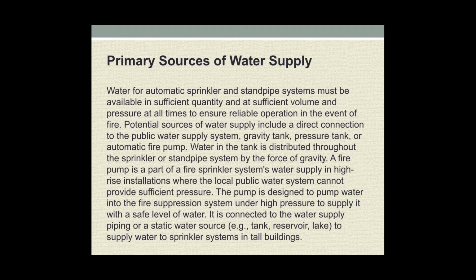Primary source of water supply. Water for automatic sprinkler and standpipe systems must be available in sufficient quantity and at a sufficient volume and pressure at all times to ensure reliable operation in the event of fire. Potential sources of water supply include a direct connection to the public water supply system, gravity tank, pressure tank, or automatic fire pump. Water in the tank is distributed throughout the sprinkler or standpipe system by the force of gravity.